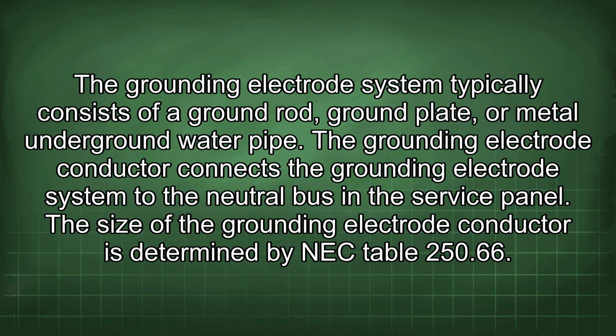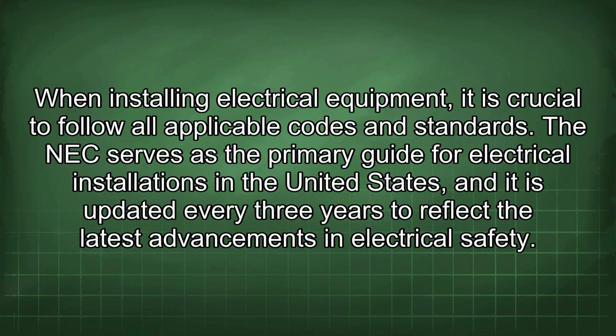The grounding electrode conductor connects the grounding electrode system to the neutral bus in the service panel. The size of the grounding electrode conductor is determined by NEC Table 250.66. When installing electrical equipment, it is crucial to follow all applicable codes and standards.